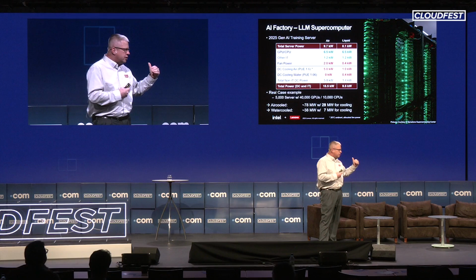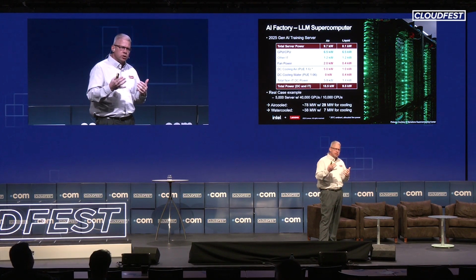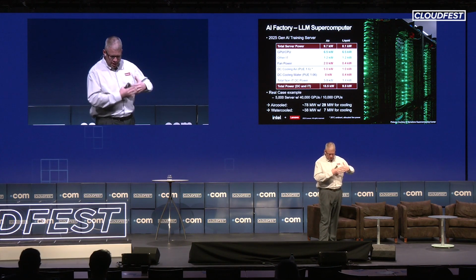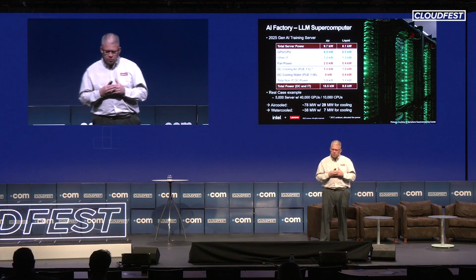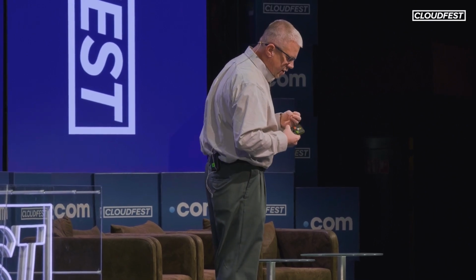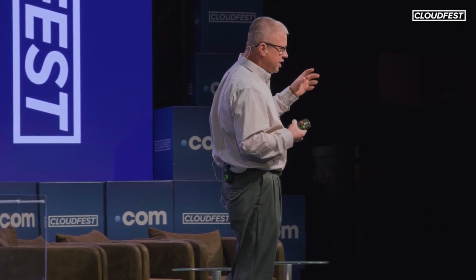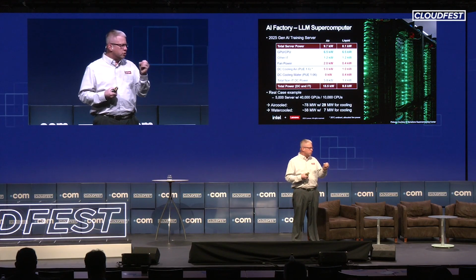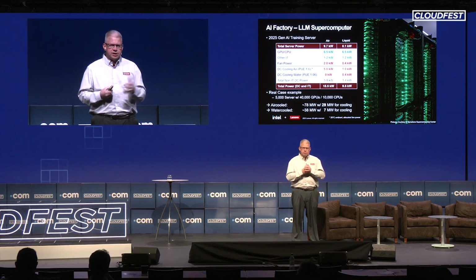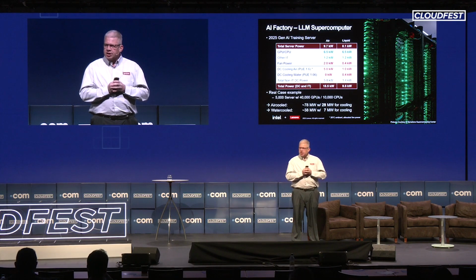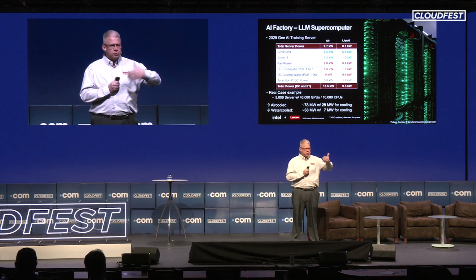Now, again, you've got to think beyond just the server and what that means from a data center perspective. When you look at what we can do with liquid, saving heat inside the data center takes that down from about 15 and a half, 16 kilowatts all the way down to about 9 to 10 kilowatts. So that's a third power reduction in what you're doing when putting out these types of AI server applications and systems.